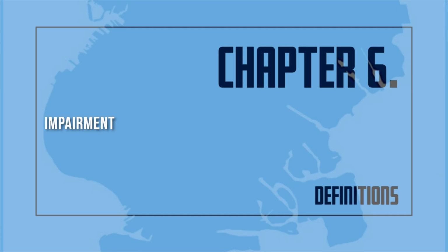Impairment. A condition where a fire protection system or unit or portion thereof is out of order, resulting in the fire protection system or unit not functioning in a fire event. Impairment coordinator. The person responsible for ensuring that proper safety precautions are taken when a fire protection system is placed out of service. The building owners shall assign an impairment coordinator to comply with the requirements of this document. In the absence of a specific designee, the owner shall be considered the impairment coordinator.